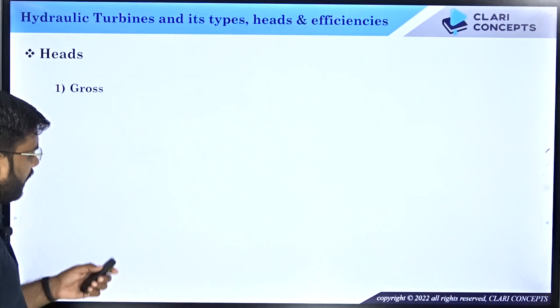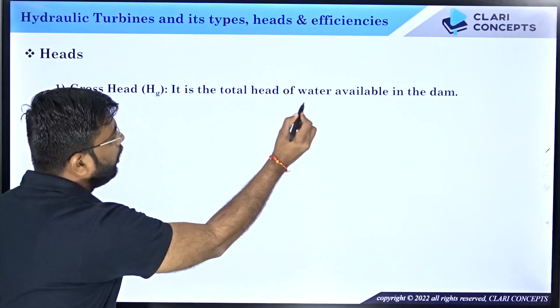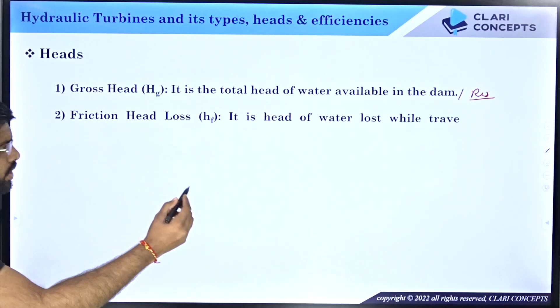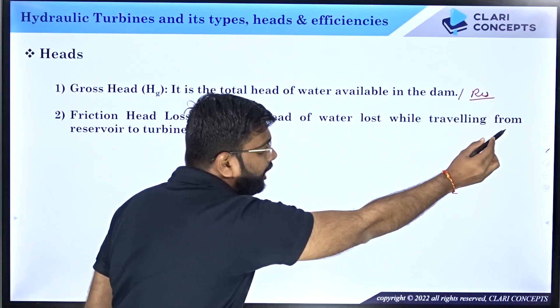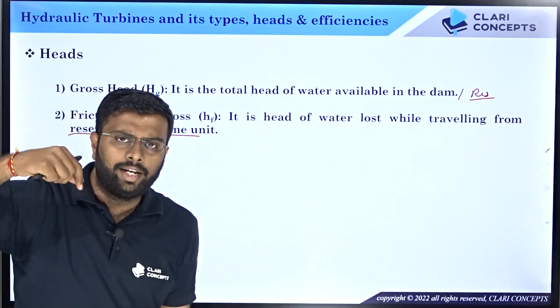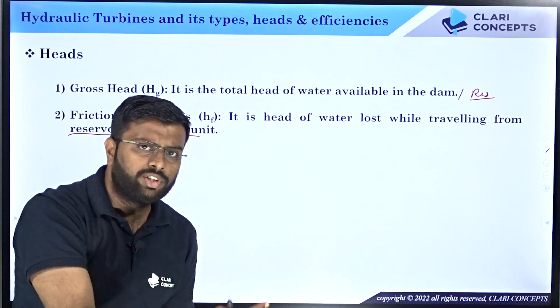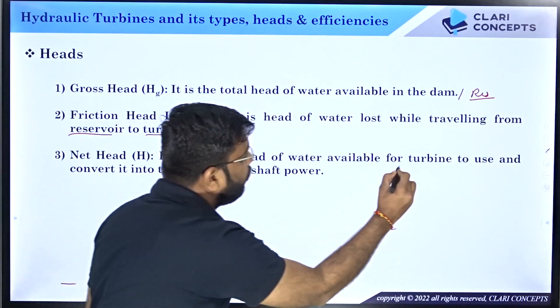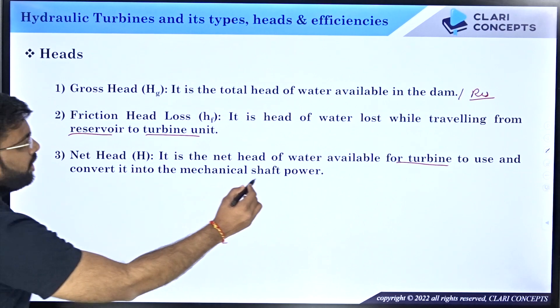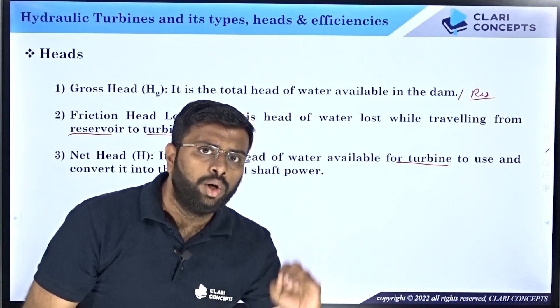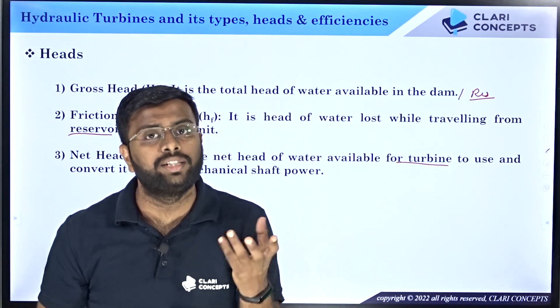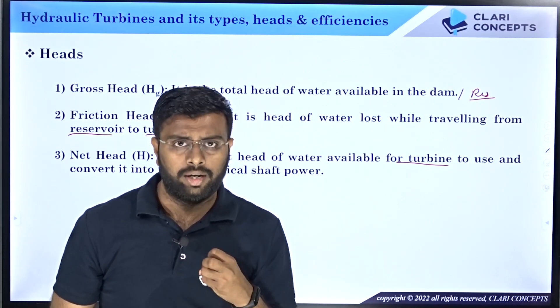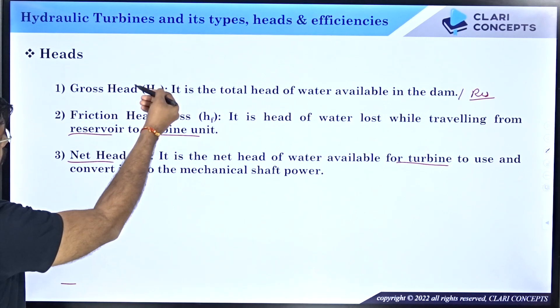So to summarize: gross head HG is the total head of water available in the dam or reservoir. Friction head loss HF is the head of water lost while traveling from the reservoir to the turbine unit through the penstock. And net head H is the head of water available for the turbine to use and convert into mechanical shaft power, which equals gross head minus friction head. That is clear.